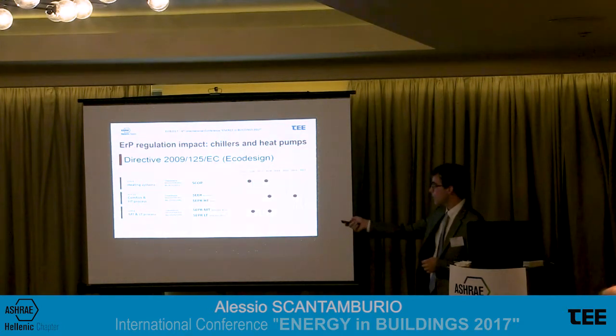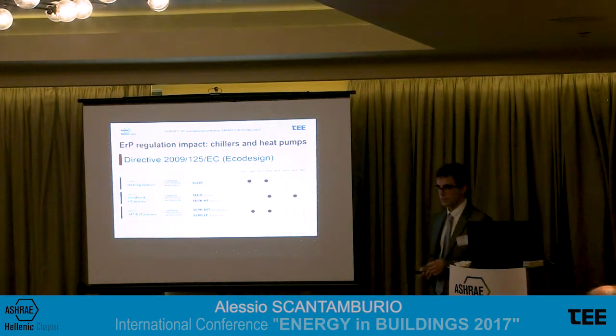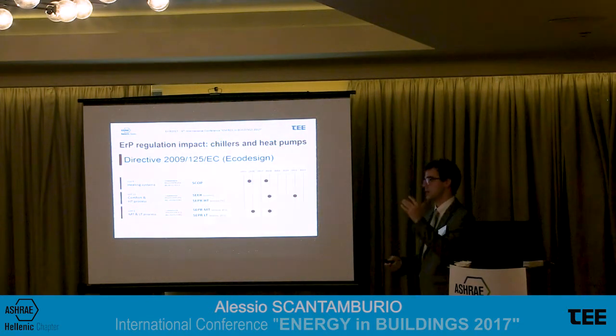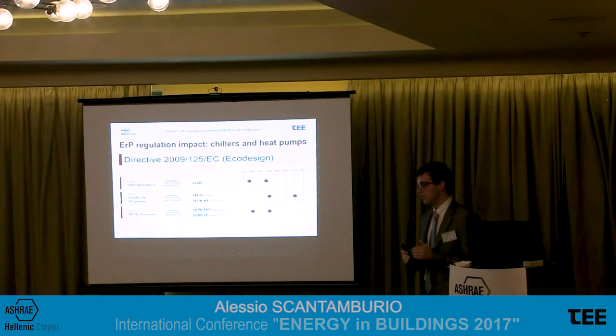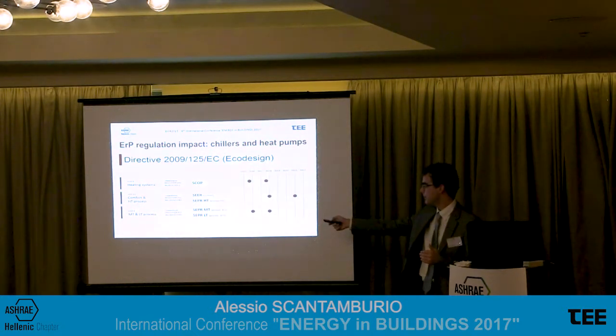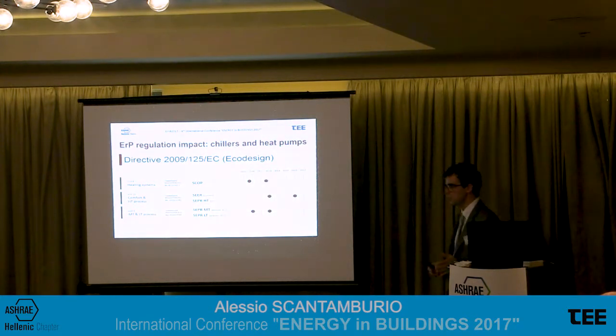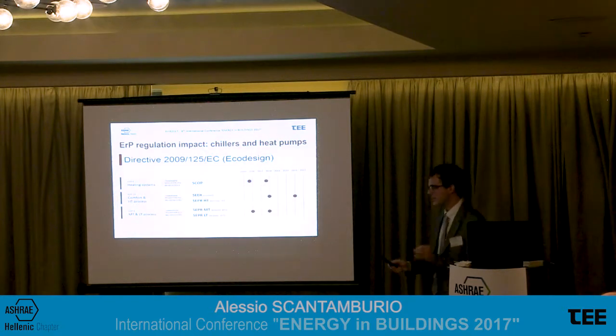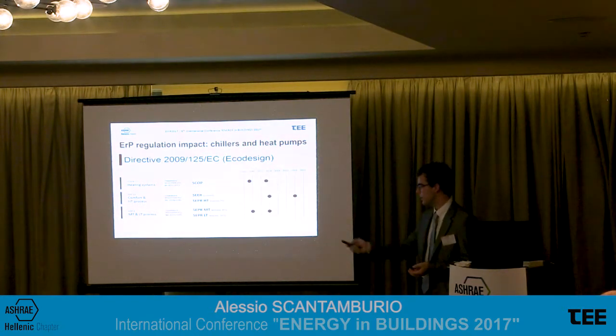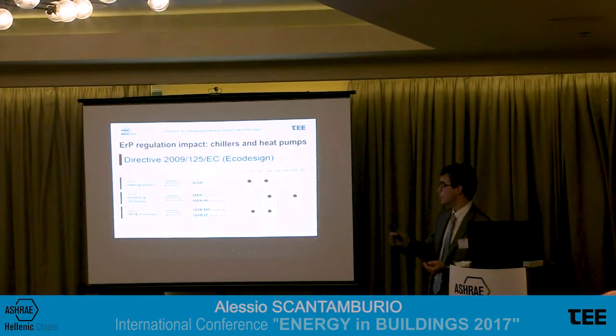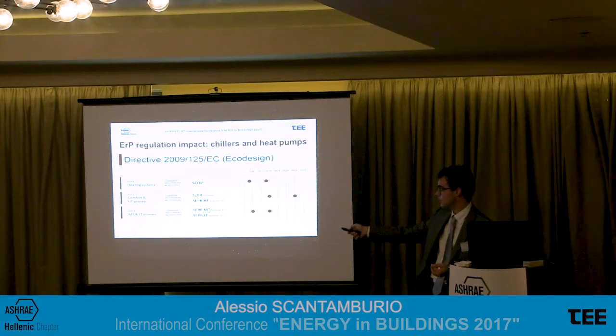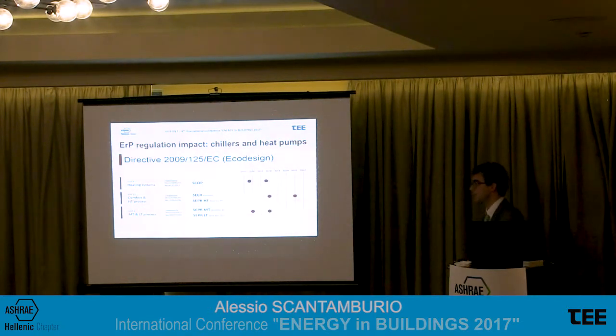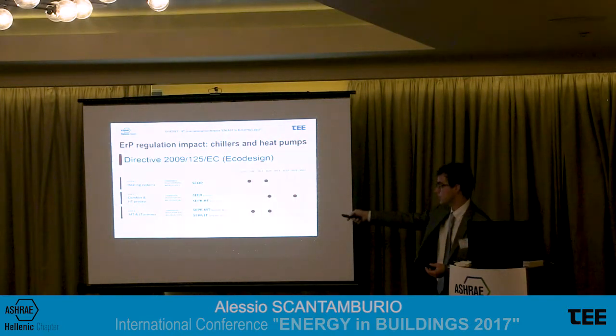Again, if we have not a comfort application, but a process cooling application, like an industry, for example, we have three main possibilities. It depends on the water temperature levels. If the temperature of the process cooling application is 7 degrees, or the regulation says between 2 and 12 degrees, but the standard condition to be considered for the calculation is 7, then we use the SEPR high temperature, which has the same time schedule as the comfort parameter.